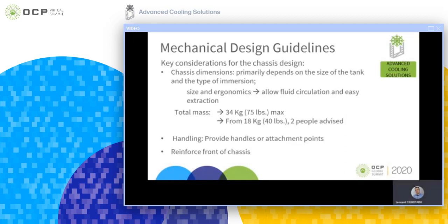Chassis dimensions. There are several different forms, sizes, and technologies for immersion tanks. One just needs to adjust to the size of the tank for which the server is designed. The important factors to bear in mind are allowing for easy fluid circulation and ergonomics, since the chassis are vertically extracted and not horizontally like a classic racked solution. In order to meet data center handling requirements, the total mass of a server with all the components installed must not exceed 34 kilograms or 75 pounds.